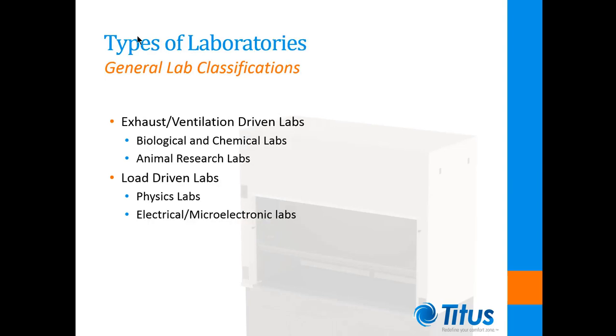Now that we have covered how laboratory ventilation is established, we can cover the two main categories of labs based on the HVAC system design. There are chemical and biological labs that typically have high exhaust rates because of the number of fume hoods used. There are also animal laboratories and holding rooms which have high ventilation rates to contain odor and meet code requirements. The other types of labs we see are load-driven labs where the airflow rates required to maintain space temperature far exceed exhaust requirements — typically physics and electronics labs with high sensible loads, and usually under positive pressurization.